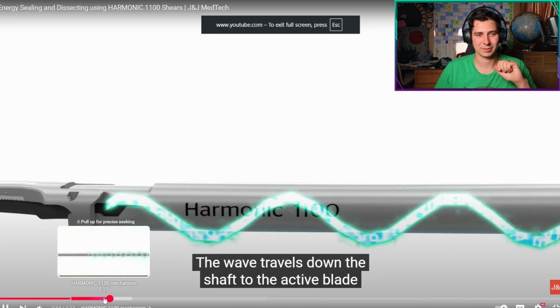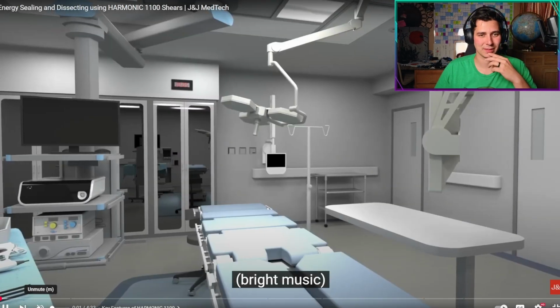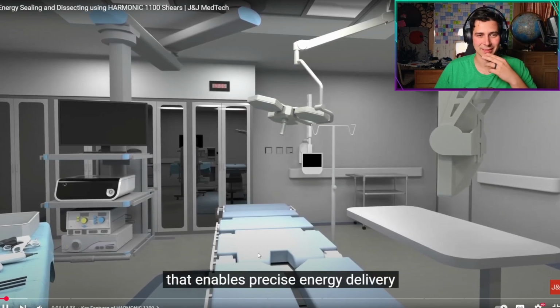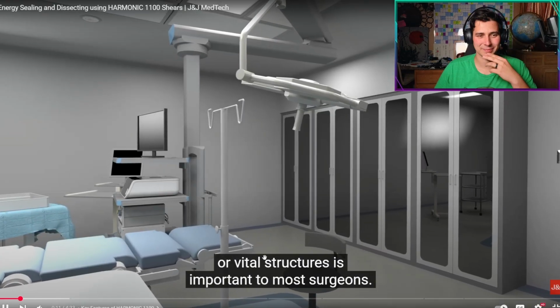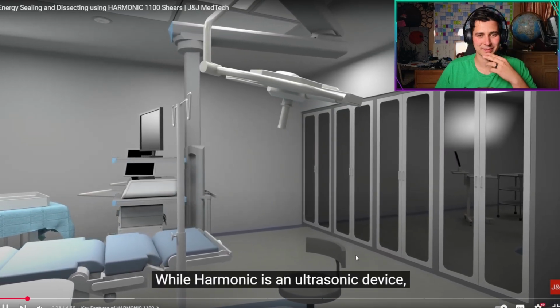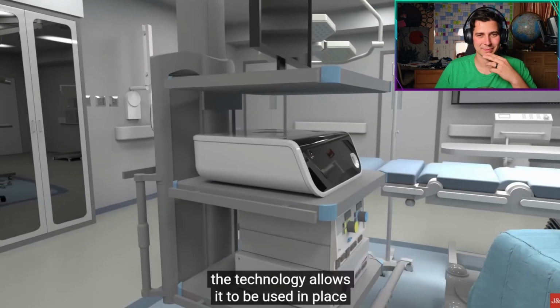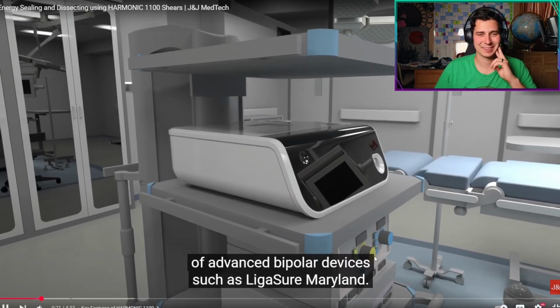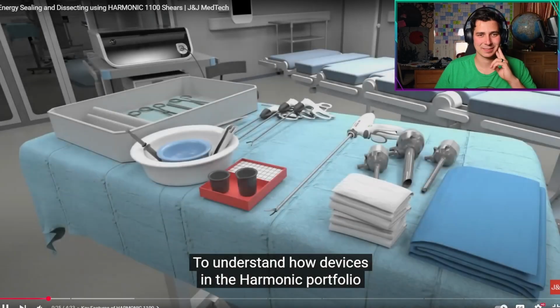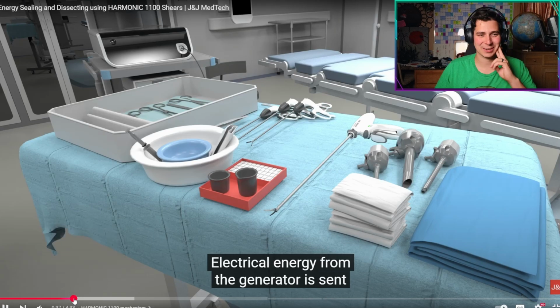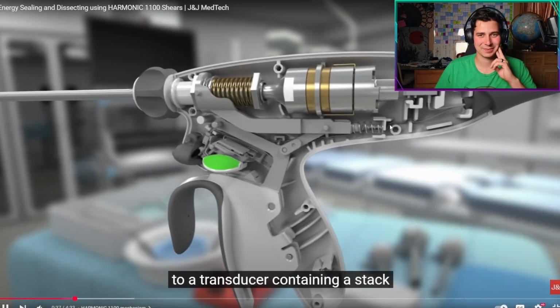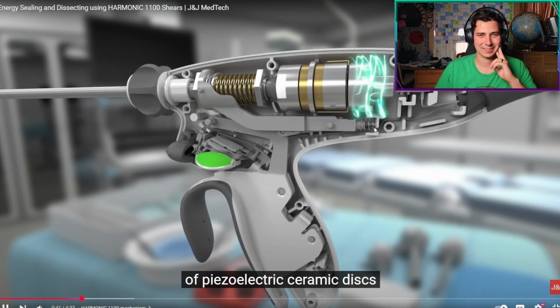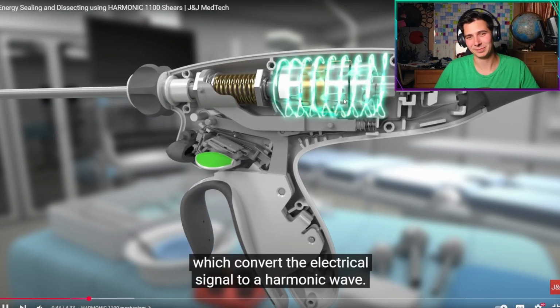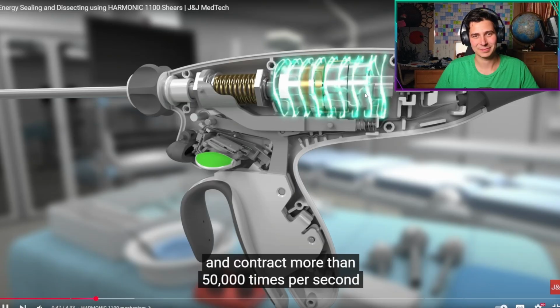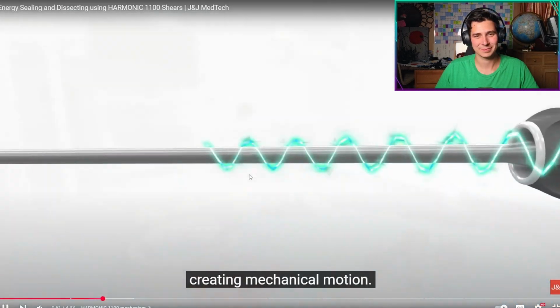The device that enables precise energy delivery to aid in protecting healthy tissue or vital structures is important to most surgeons. While Harmonic is an ultrasonic device, the technology allows it to be used in place of advanced bipolar devices such as LigaSure. To understand how devices in the Harmonic portfolio can help achieve this, explode it. Electrical energy from the generator is sent to a transducer containing a stack of piezoelectric ceramic discs, which convert the electrical signal to a harmonic wave. This causes the device's active blade to expand and contract more than 50,000 times per second, creating mechanical motion.